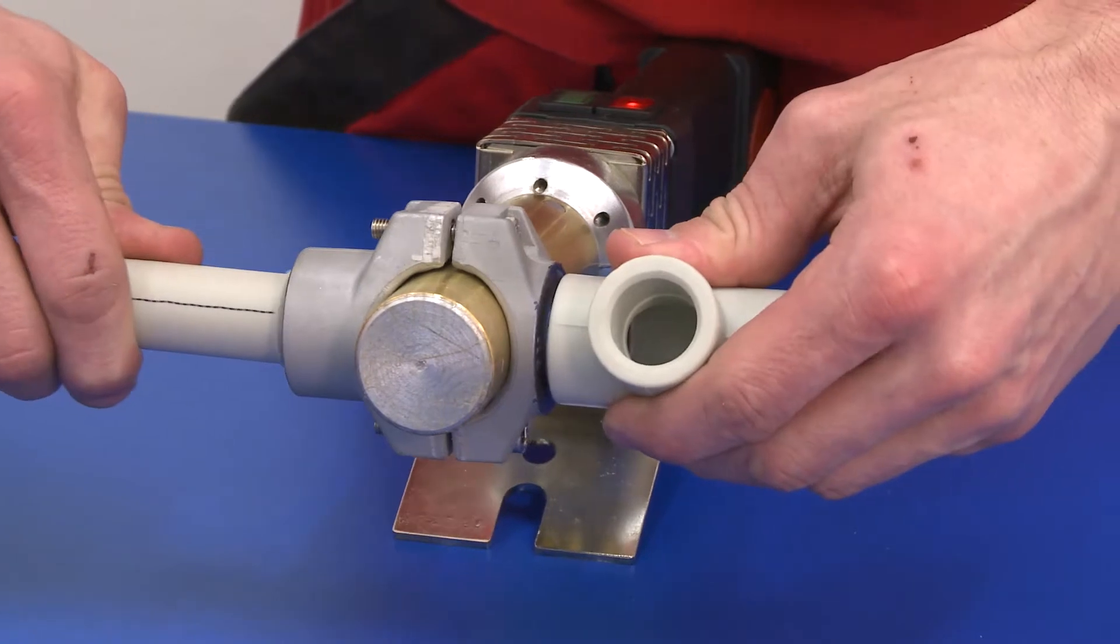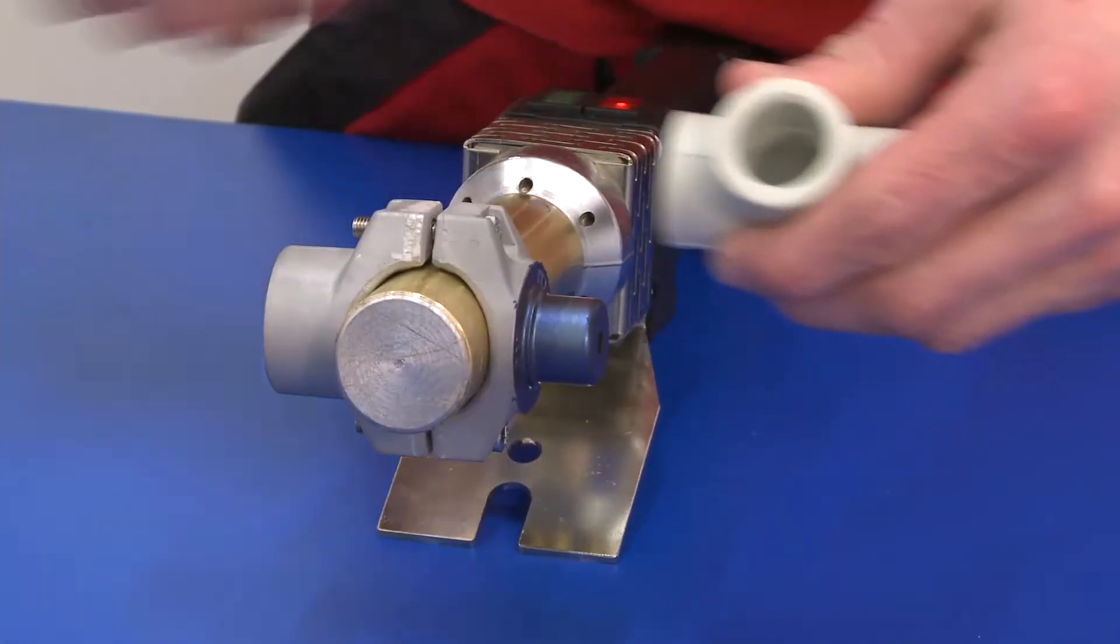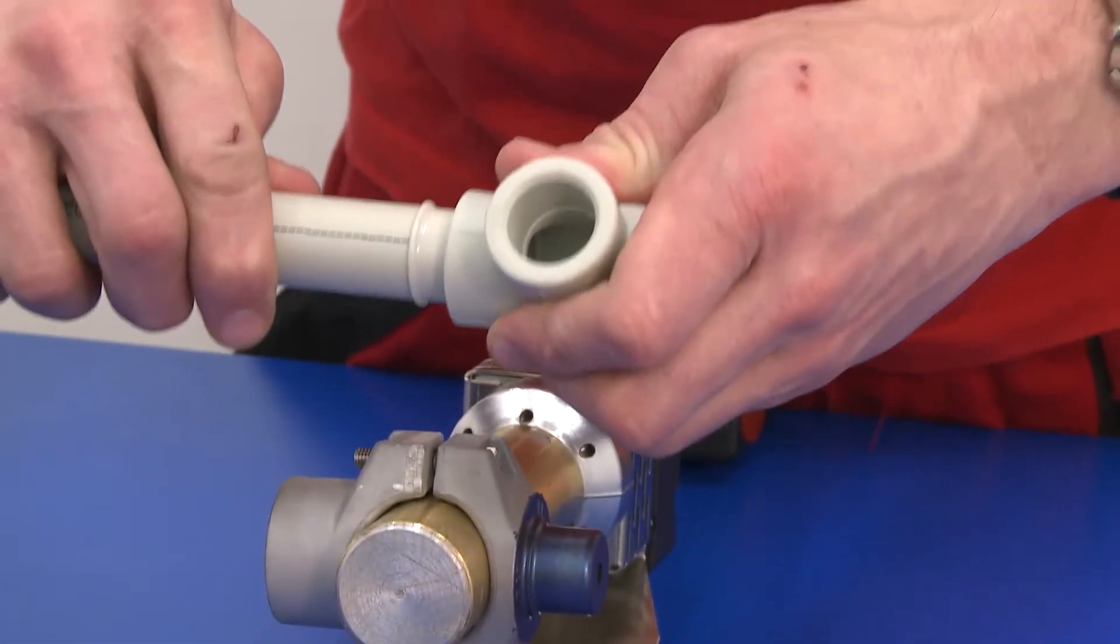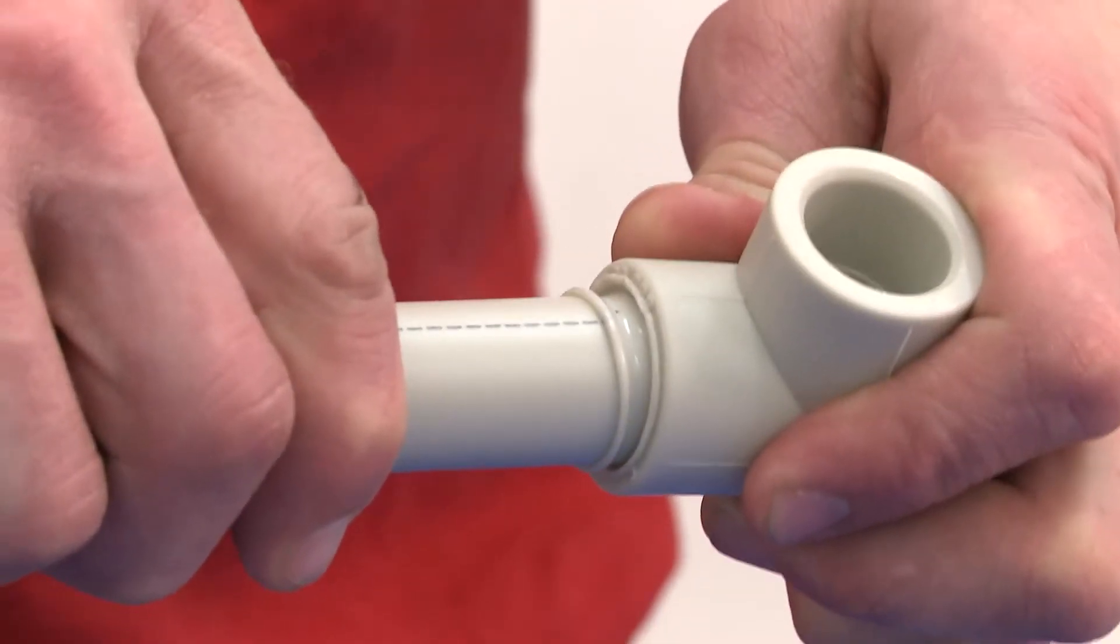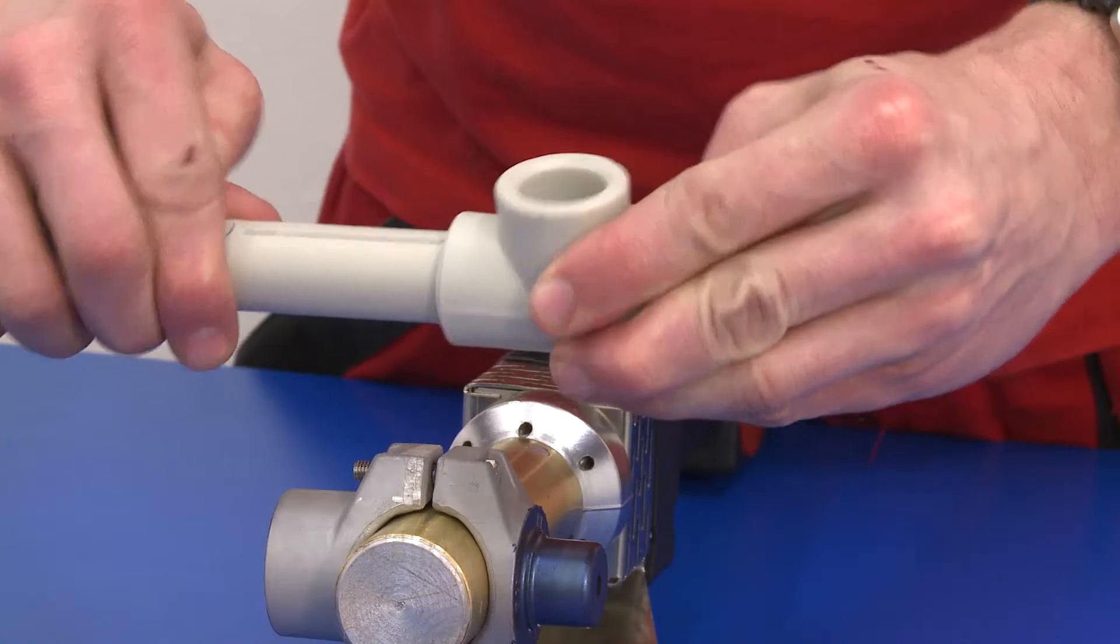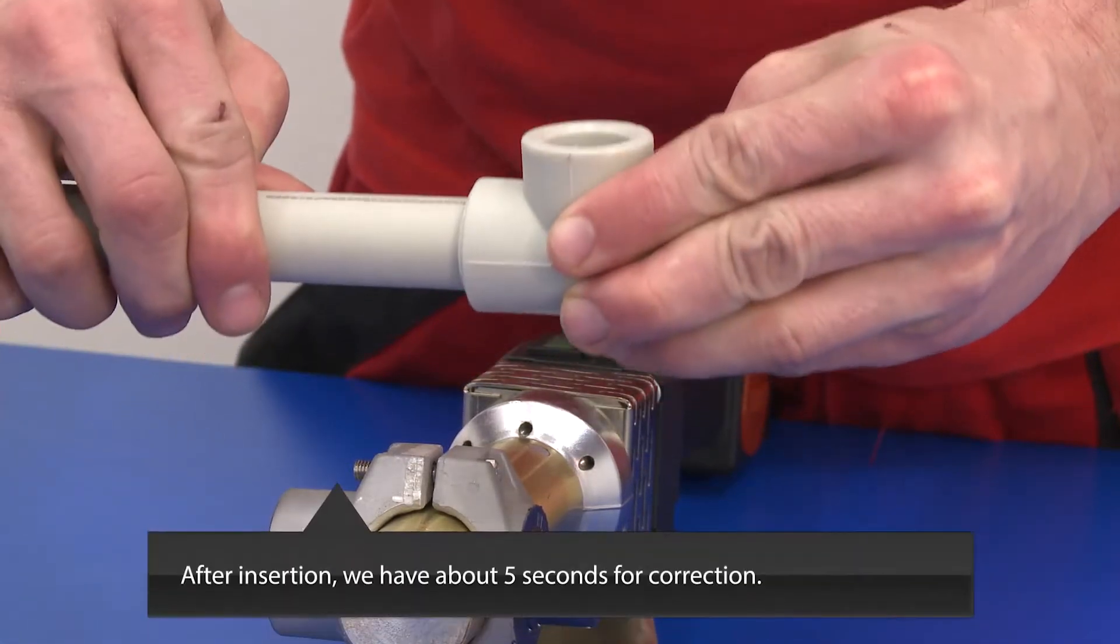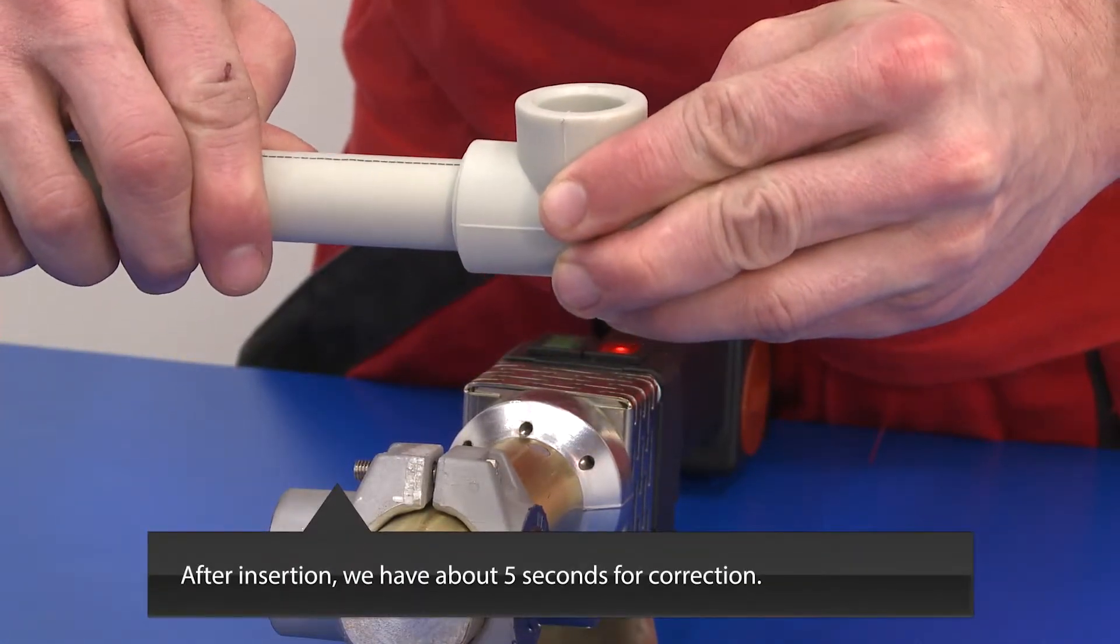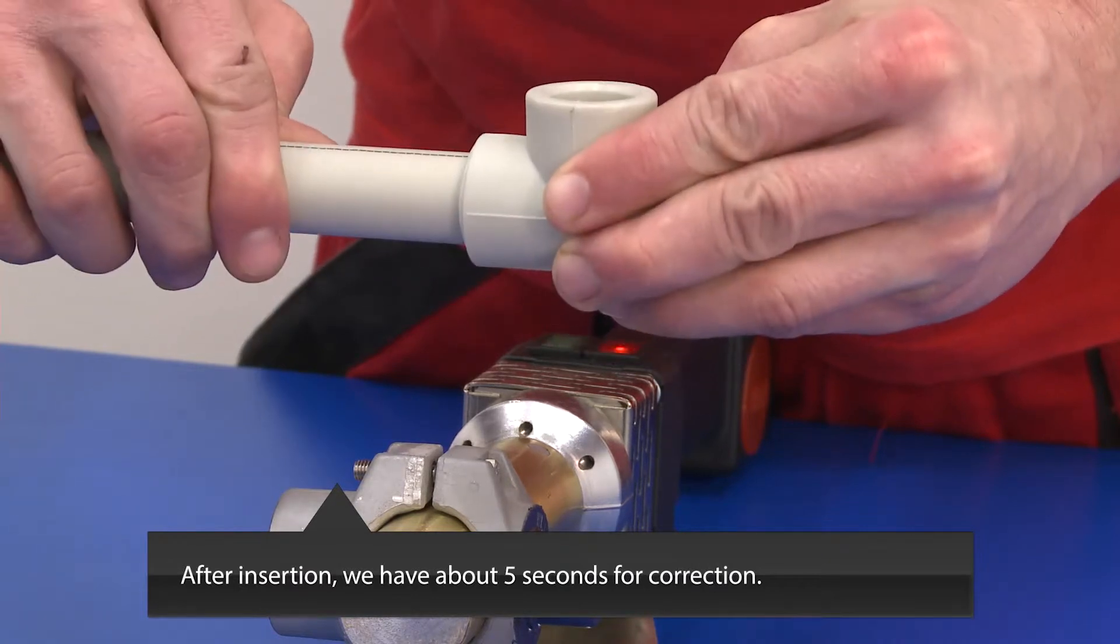After the warm-up time the pipe and fitting are removed from the attachment. The connection is performed by pushing the tube by slow steady pressure axially into the socket of the fitting without rotating. Now we have approximately five seconds for possible correction.